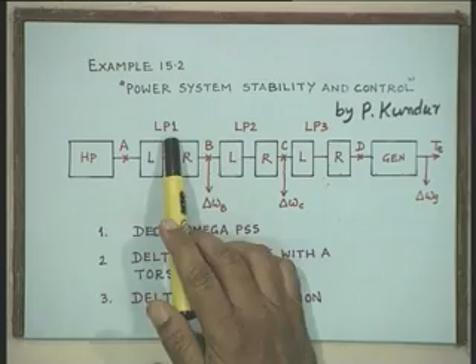Now, to overcome the problem of excitation of torsional modes due to adverse interaction between the excitation control and torsional oscillations, studies were conducted by putting a speed sensing device at the end of the generator. That is, suppose you put the speed sensing device here, the speed sensed is delta omega g. Another location identified for sensing the speed is between LP2 and LP3, that is delta omega c, at this location C. Now, C forms a coupling between the LP2 and LP3 sections. Similarly, studies were also carried out by sensing speed at the coupling between LP1 and LP2.